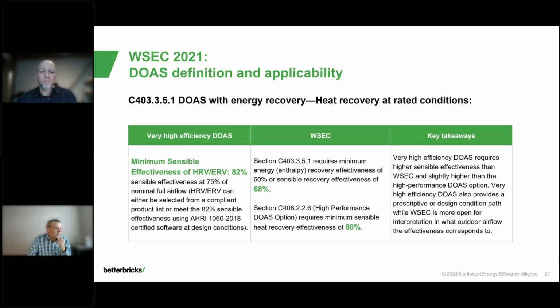And in this one, it's about the ERV HRV, right? So again, I think I've noted it, but in NEEA's program, we require 82% sensible effectiveness on the ERV HRV. In Washington code, their base is 68%, so obviously the 82% meets that. But the other thing is that in their high performance option path, they require 80%, so we meet that as well with what we have as a system. So not only does it meet the base, but it also is better or meets in the performance path as well. So next slide.